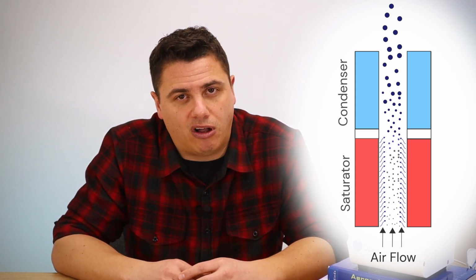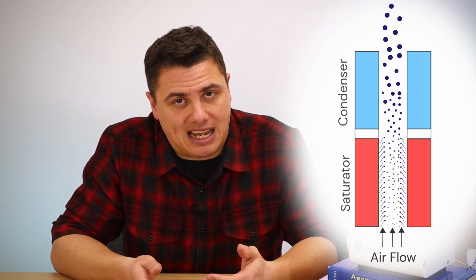In our device, we do the same thing, but instead of using water, we use isopropyl alcohol, sometimes called rubbing alcohol. And what we do is we have 2 tubes in series. We have a first tube called a saturator, where we pull air in and we expose it to warm, wet walls, in this case wetted with isopropyl alcohol, where the vapor goes into the airstream. We then pass this warm airstream, although it's not really humid, it has isopropyl alcohol, into a cold, chilled section we call the condenser. There, because it's cold, the vapor begins to condense out onto particles that are in the air, and they grow them from maybe 10 nanometers to a few microns.